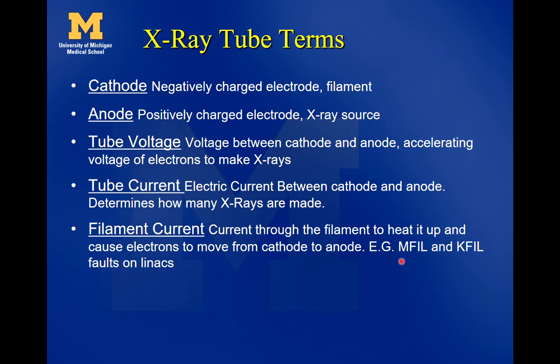You may see M-FIL or K-FIL faults on the linac. The 'fill' part of that stands for filament. The klystron has a filament in it to create electrons, and the magnetron has a filament in it. When you see M-FIL and K-FIL faults, you should think that some current should be running through a filament to make it hot enough to produce electrons — and it's not doing that, so the linac is faulting out.